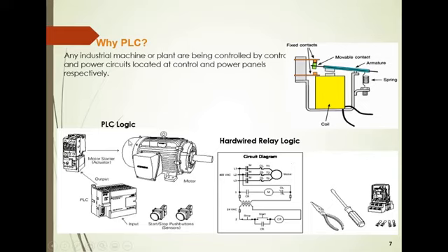In case of PLC logic, you need a contactor and OLR, PLC, motor and push button. The push button will be connected to the PLC and the contactor will be connected to the output. It will generate the output to the motor and run the motor. So you press the start button, the motor will start. Stop button, the motor will stop. So this logic will remain in the PLC.